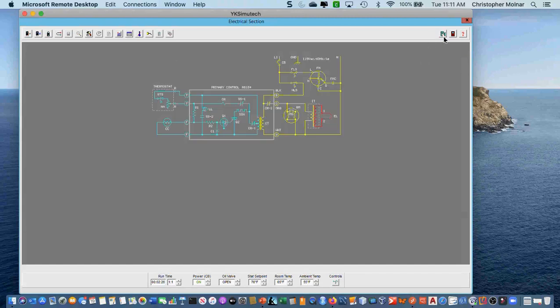I can go to my electrical side, and I can use an amp clamp. I can take the amperage of my blower motor. I can click on the meter, and I can take an amperage of my burner motor. I can also take the amperage at my main disconnect, which is coming in from L1. It's labeled CB. That's a circuit breaker. So I can see the amperage of the entire piece of equipment.